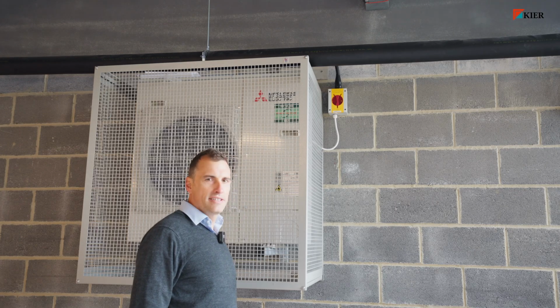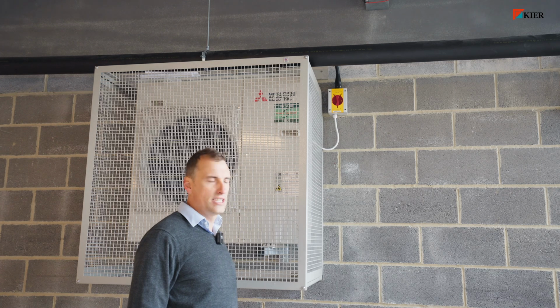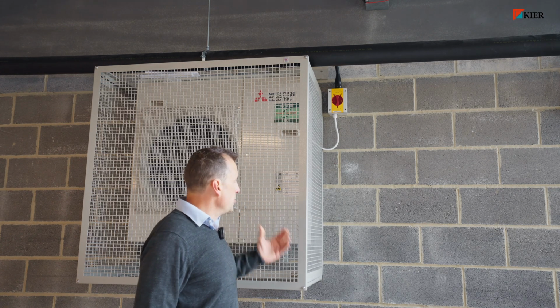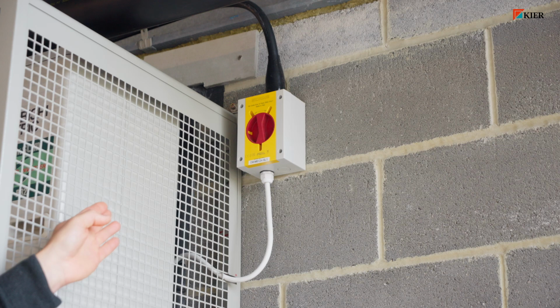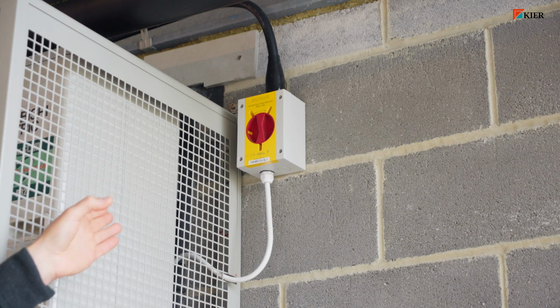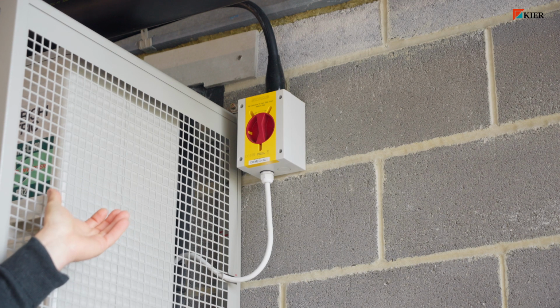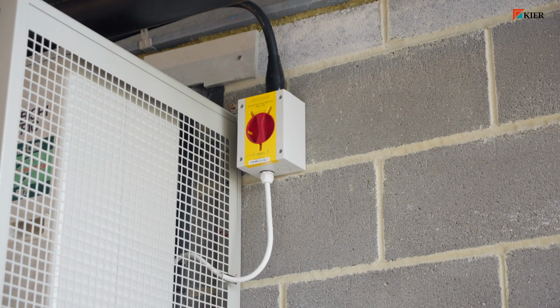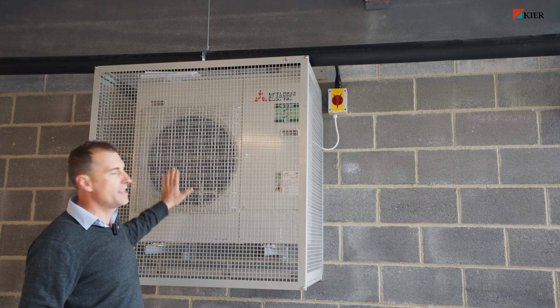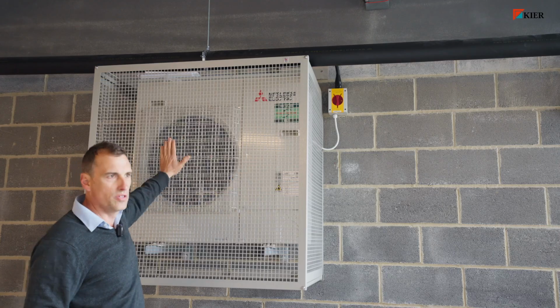When you're looking to maintain the comms room AC units, this unit just needs to be isolated from that switch up there. At the moment it's in the on position. You rotate it to the left to the off position. That will then render this disabled, and you can then conduct any of your maintenance on this unit.